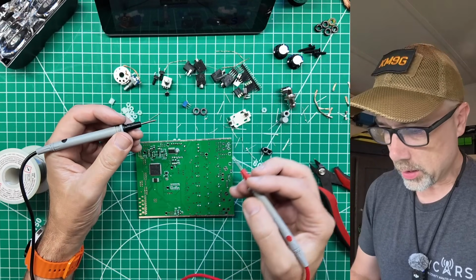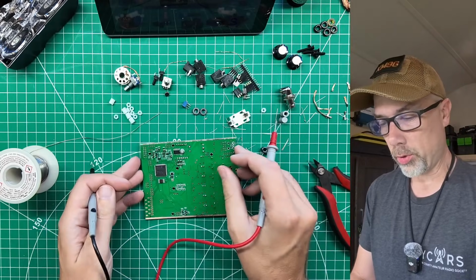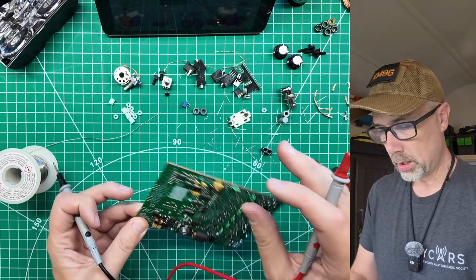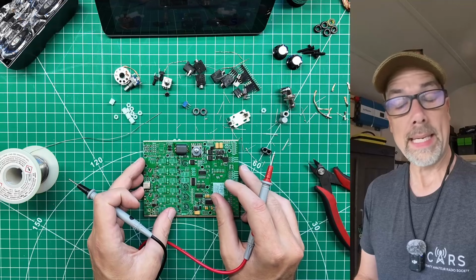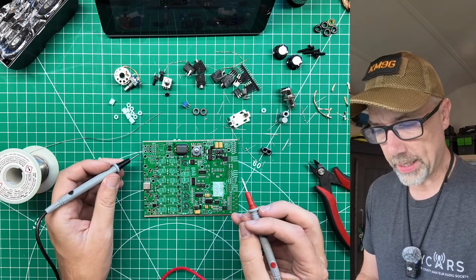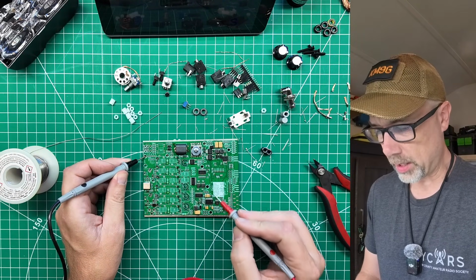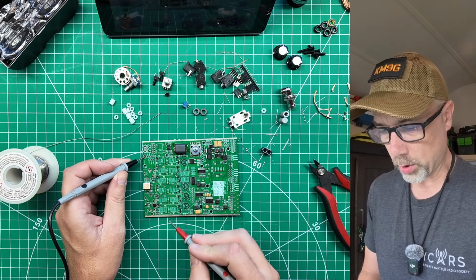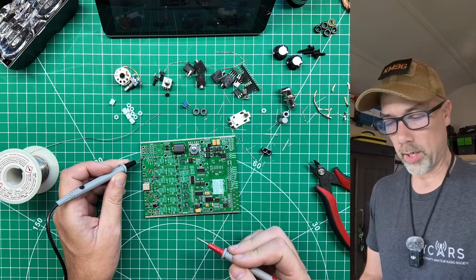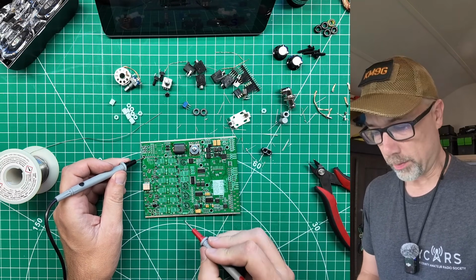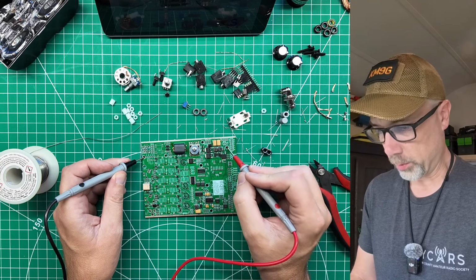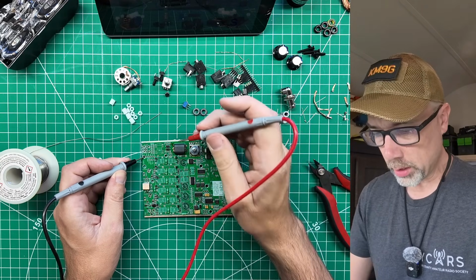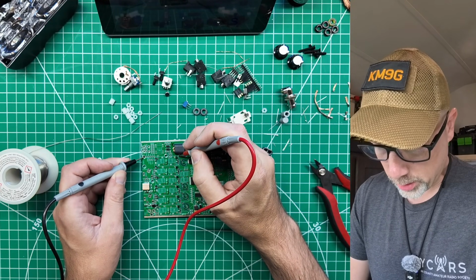Yeah, that takes care of the 3 primary windings. Now we have the 2 secondary windings, and they're supposed to be able to talk through ground, and his test points for that are test points B. He says take any ground. So find a ground. Usually it's these mounting holes here all over the board, or it's this edge rail is a ground. First verify that you've got a good ground by touching any one of the other grounds all over the board. Now that you have a known good ground, you can check that capacitor that he's talking about on the edge.